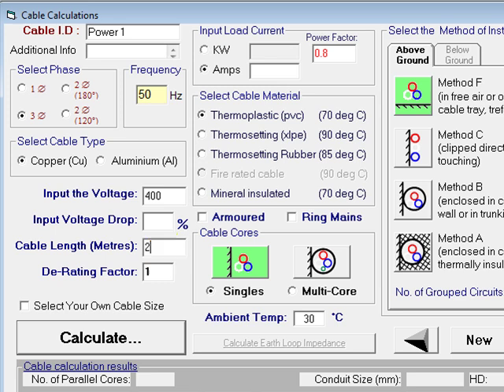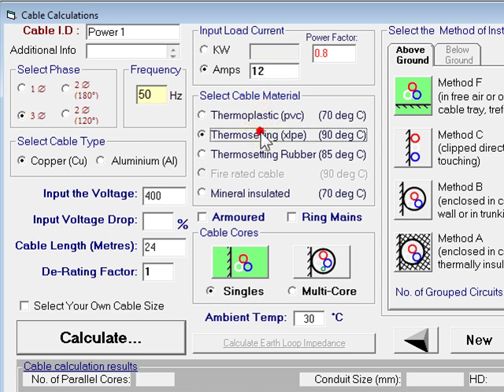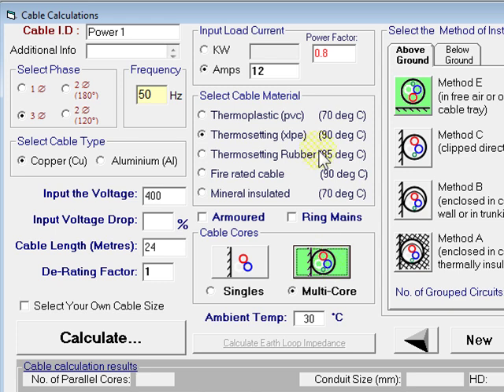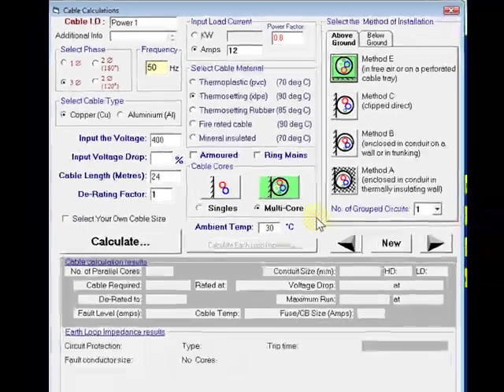The length of the run is 24 meters, derating factor of one, and the current on that circuit — make that 12 amps. XLPE 90 degrees C, multi-core, on a cable tray. That's all the information we need.